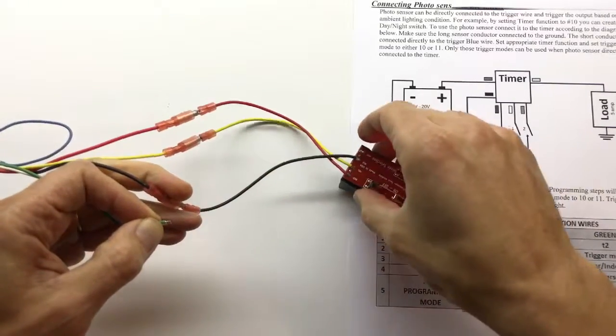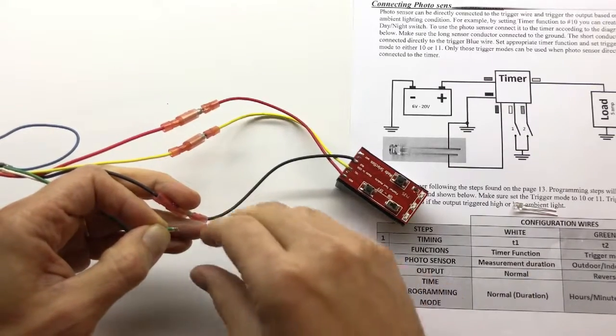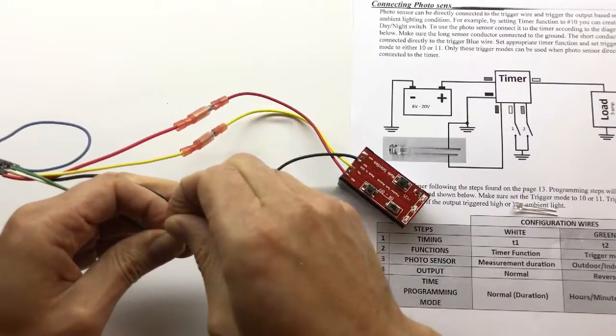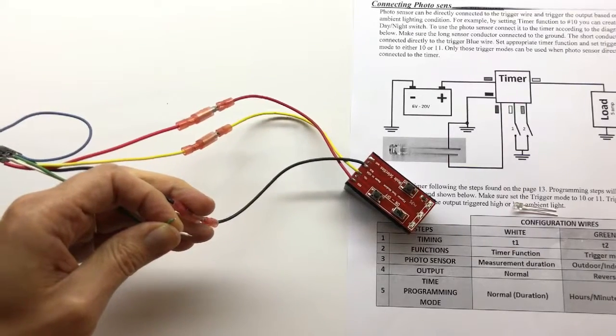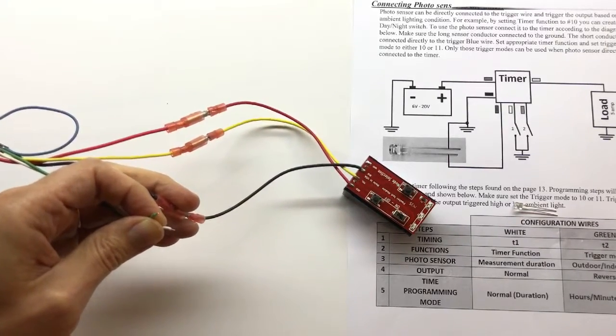Next step is the measurement duration. This is how long the sensor is going to measure the light. So if you want very sensitive circuit, you set it to a very short time, let's say second. If you want, for example, for the outside lighting circuit, you probably want the sensor to have the threshold of a couple of minutes.